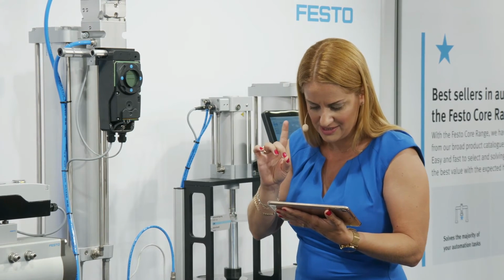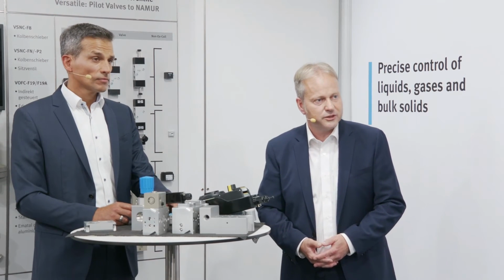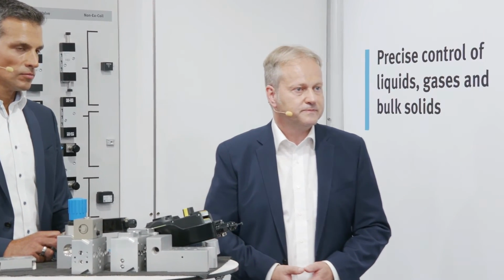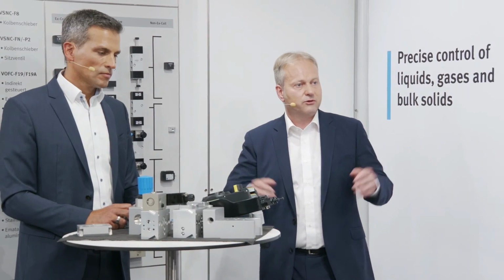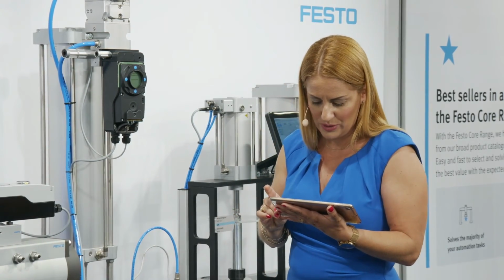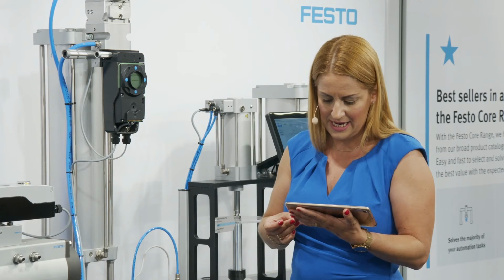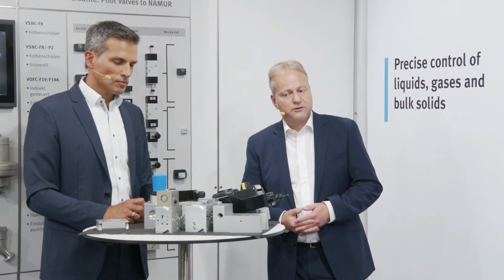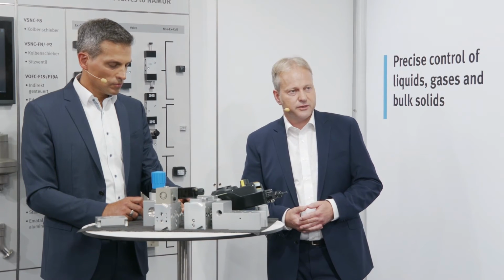I hand over. What type of Ex certificates do you offer? It's explosion protection, intrinsically safe explosion protection. And also for dust, we have an ignition protection type for dust-tight housing. Is it available with international certification? Yes, sure. We are planning also international and all other local certifications. Perfect. I hope we still have time for that. We do. With this redundant construction available, can the whole VTOP system reach SIL3 or even SIL4? We reach SIL3 at least, with some redundancy. And SIL4 depends on the application.